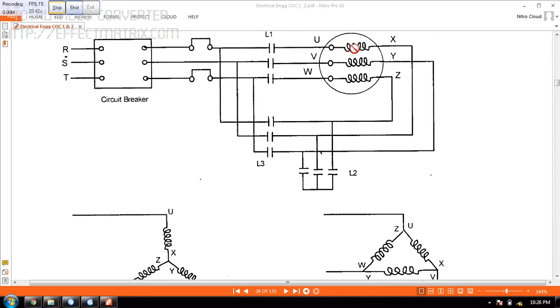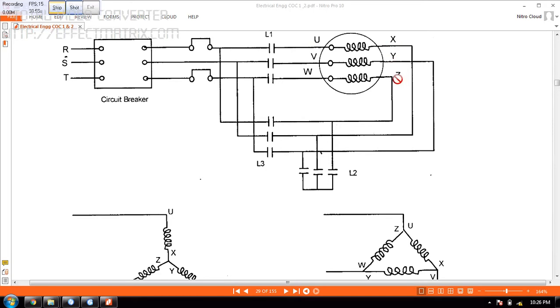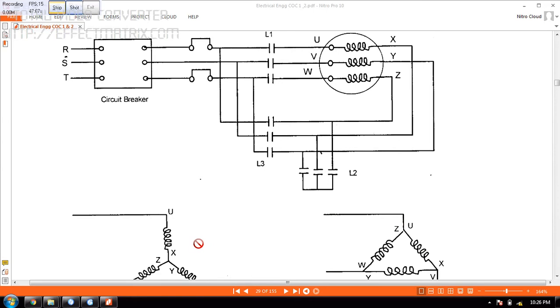You can see there are 3 coils. This is the 3 phase motor. You have U, V and W on one side. You have X, Y, Z on the other side. So to start in Star then change over to Delta. When you start in Star it will draw one third the current and torque. Then we change over to Delta using the timer.